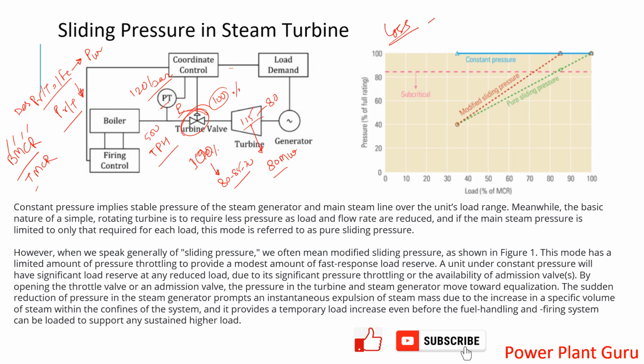What I will do is reduce only the upstream boiler pressure, so that this valve is always fully open and I am not incurring any throttling losses here. This operation is called sliding pressure.